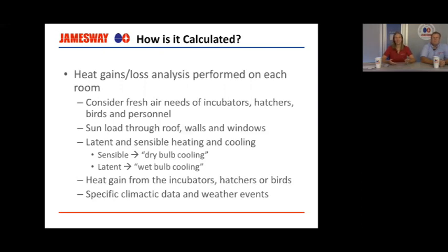And then is there any heat gain to the room from the equipment inside, from incubators, from hatchers, or from the birds, right? We're looking at 1 BTU heat production per chick in the chick room. So 500,000 chicks, that adds up to a lot of heat very quickly. And then other specific climate data, weather events, things that may not be apparent right away if you're not from the area.